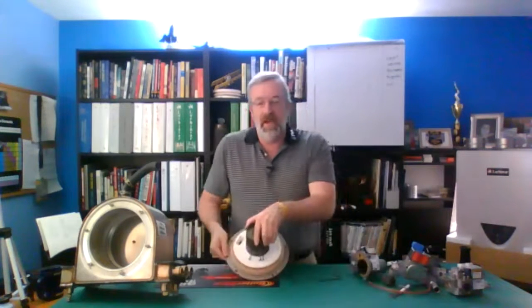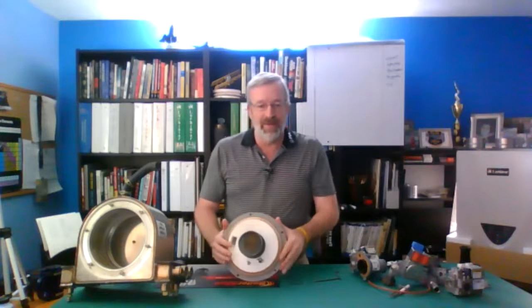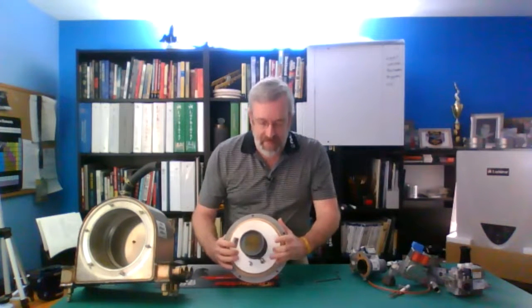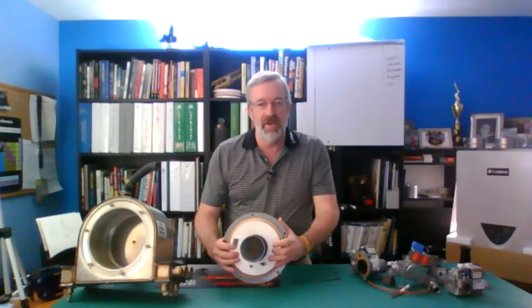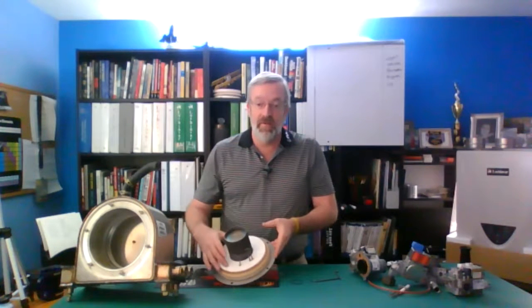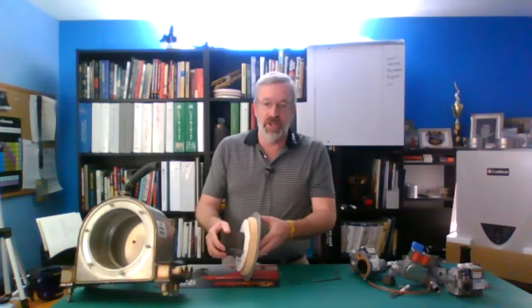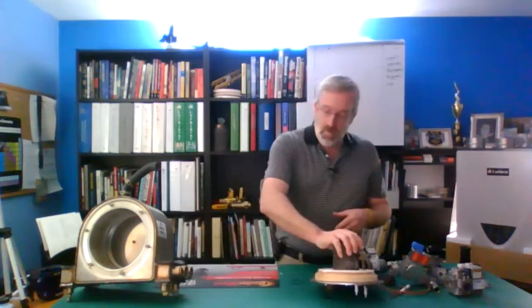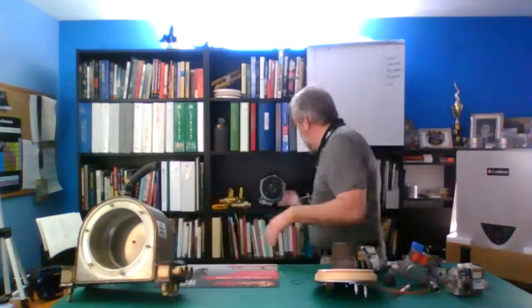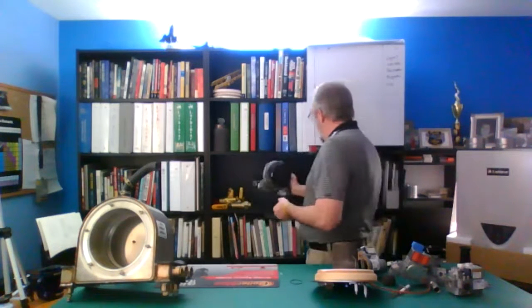Talk a little bit about the refractory here. When you first go to pull one of these out, this refractory may stick in the top of the heat exchanger. If it does, take your igniter and flame sensor out first, and that way you can leave this down in the top of the heat exchanger and pull the rest of it out, okay? And free it out, because if you try to yank it and twist it, you could damage it. If you damage this, you will need to replace it because that's really the protection for this top cover. This one here has one as well. It would normally be right here to protect this door. All right.